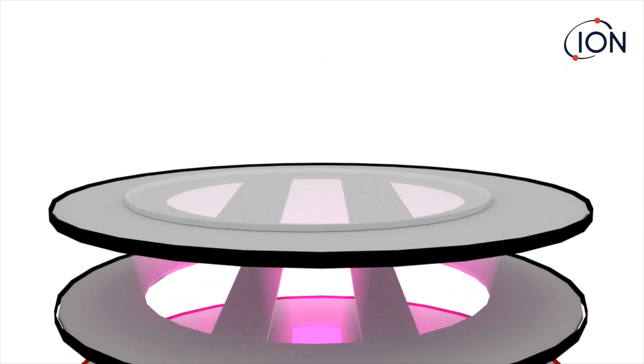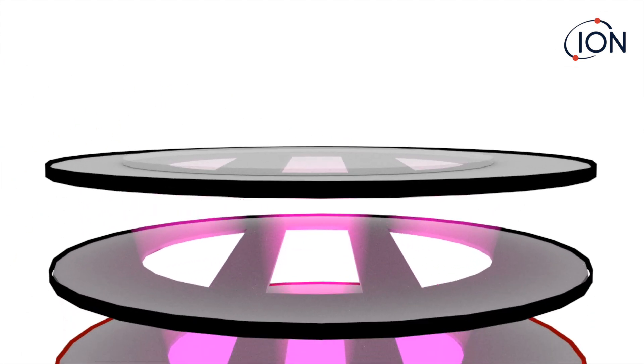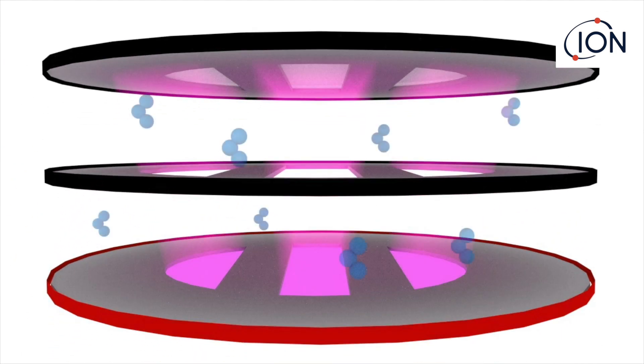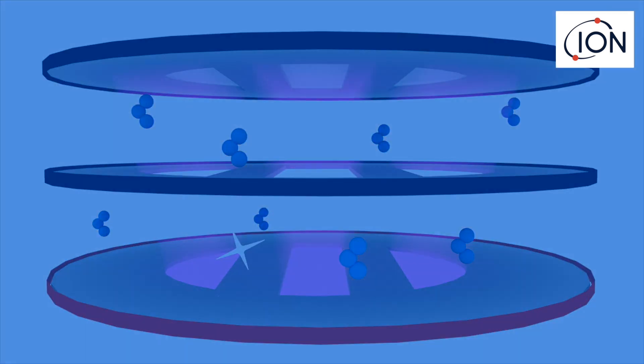The Mini PID also has an anti-contamination filter. This blocks airborne particles entering the detection chamber and helps retain tiny amounts of ozone generated in the chamber. Ozone actively cleans the electrode stack, ensuring optimum performance is maintained.